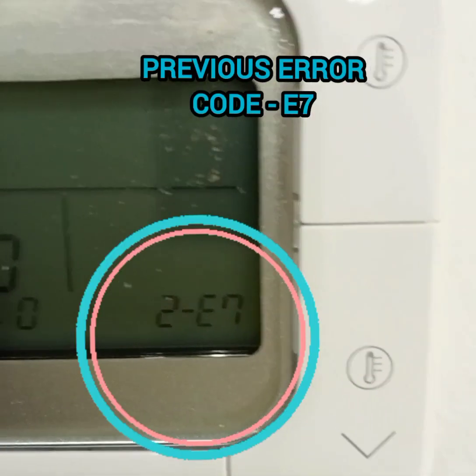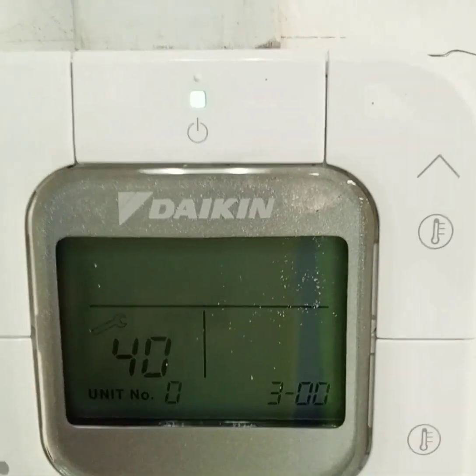After entering mode 40, the error codes are shown automatically. The first previous error code is U2 - so error code 1 is U2. Press the up button to see the second error code: E7. Press again for the third error code - number 3 shows nothing, so this system has only two error codes. This unit has been installed for maybe one year or more.